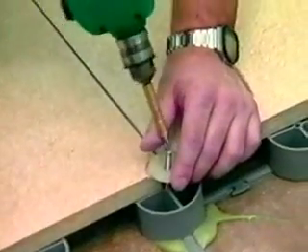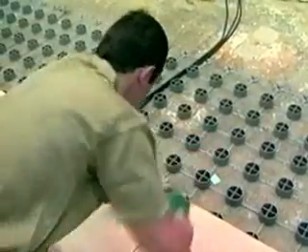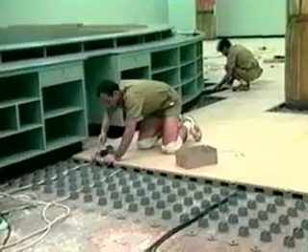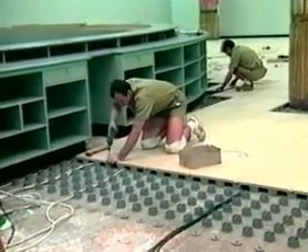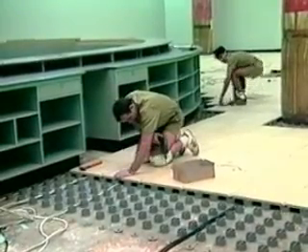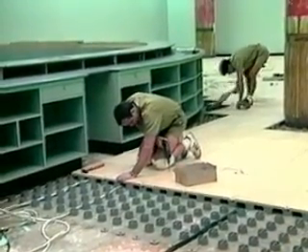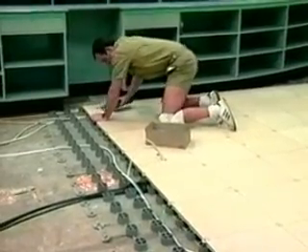The particle board panels are placed carefully onto the understructure and loosely screwed down with 2 of the 4 nylon corner clamps. The previous row corner clamps are tightened. For every square meter or square yard of Cablefloor, there are 40 support cylinders, each capable of supporting 1 ton. Under each row of panels, there are 3 easily accessible cable channels, which provide immense cabling capacity for telephone, power, and data.